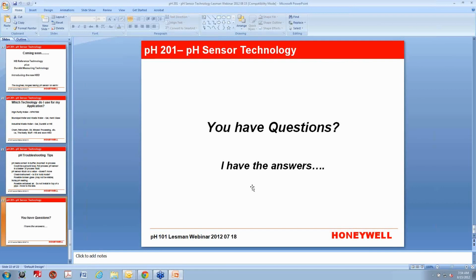Now, the other thing we had to do in that application was set up some automatic cleaning, because even with that flat profile, the sensor would still get fouled like every day. They would have to take it out and clean it once a day for sure, if not more often. A lot of times they were doing it once a shift. Because this is a ball valve insertion style, you could take it out and test it and calibrate it. What they did was insert little tubes with hot water into the pipe, and they stick out until they're about maybe 1.5 inches from the face of the sensor. The sensor has a lock on the back, so you can only push it in exactly as far as it's supposed to go. I think every hour this device just squirts hot water onto the face of the sensor.